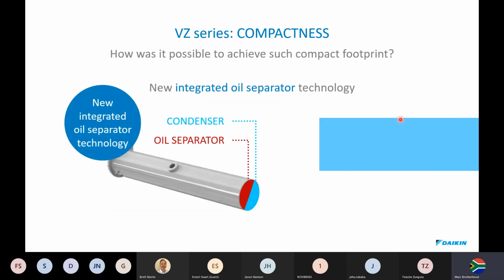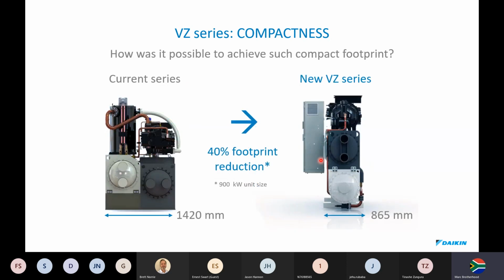We've also, this is what I said to you, I'd explain the integrated oil separator technology. Some manufacturers use what they call cyclonic separation, where the gas goes in a centrifuge effect, but as it spirals down in the centrifuge, it loses pressure, and pressure drop and temperature drop means loss of energy efficiency. So Daikin have come up with an oil separator which is built into the condenser now, which is very low oil carryover and, as I mentioned to you as well, very low pressure drops within the condenser, which means good efficiency. You drop the pressure, you drop the temperature, or increase the temperature depending on what refrigeration process you're talking about.